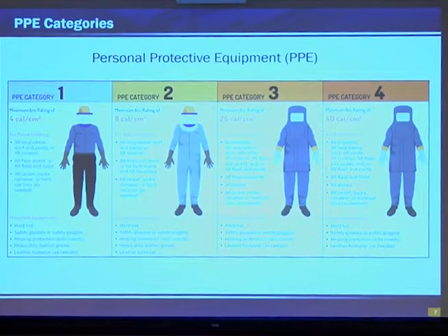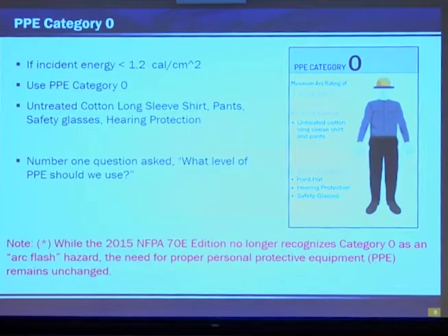Does anyone notice that PPE Zero is not shown up here? While the 2015 NFPA 70E edition no longer recognizes Category Zero as an ArcFlash hazard, the need for it still remains. If incident energy is less than 1.2 calories per centimeter squared, we still have to wear the proper clothing. Now, what does this clothing consist of? Well, it consists of untreated cotton long sleeve shirt, untreated cotton pants. Notice I say untreated cotton and not ARC-rated cotton. And why am I talking about PPE Zero if the 2015 NFPA 70E does not recognize it? Well, TxDOT still recognizes PPE Zero. If you look at our online manuals, we still recognize PPE Zero.